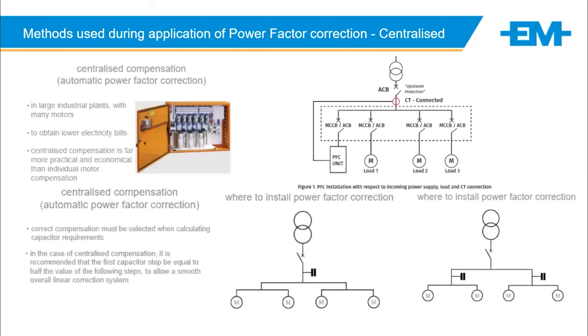So for methods used during application of power factor correction, there's kind of two ways. I'd like to stick to the image on the right. So I've got my transformer coming in. I've got my connection point, my ACB. I've got my measuring point, which is my current CTs, which is connected to my power factor system. The power factor system is injecting anywhere on that bus bar. So the CTs are monitoring the current flow and the phase angles, and it's telling the controller, hey, I need so much reactive power, so much. And it starts bringing in the banks via contactors.